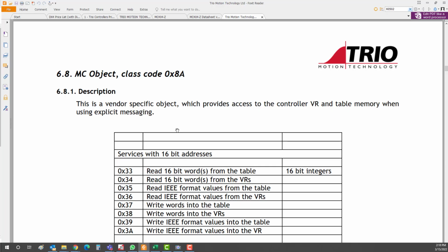So after having that AOI, you will be able to connect the Trio controller to Allen Bradley plug and play, and we will have a document for that, which sets up all the necessary communication and everything automatically, so you don't need to do anything on that. Just plug and run it, and just pick the right address on the PLC side. That's it. It's very easy actually.